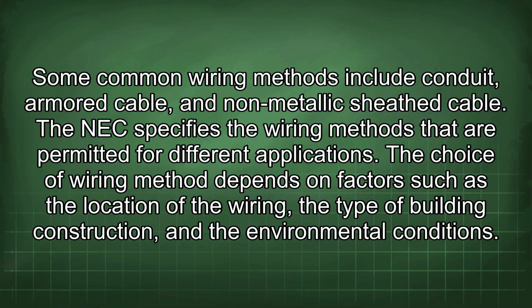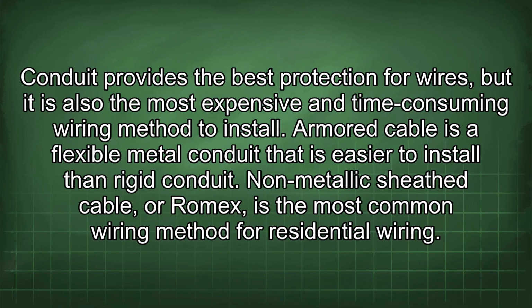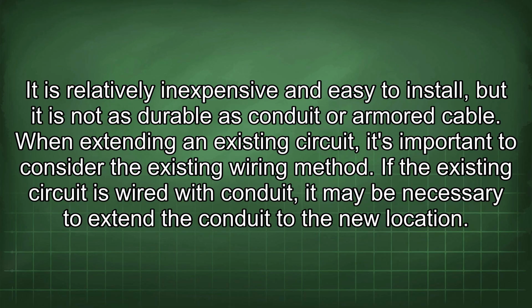and the environmental conditions. Conduit provides the best protection for wires, but it is also the most expensive and time-consuming wiring method to install. Armored cable is a flexible metal conduit that is easier to install than rigid conduit. Non-metallic sheath cable, or Romex, is the most common wiring method for residential wiring. It is relatively inexpensive and easy to install, but it is not as durable as conduit or armored cable.